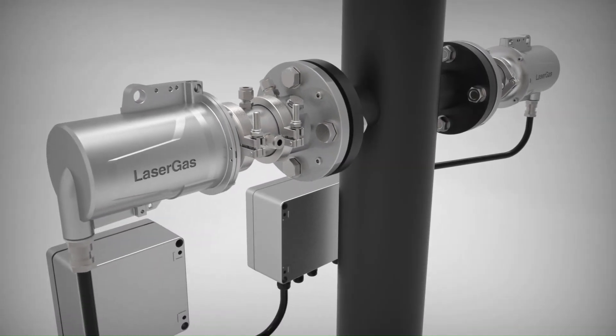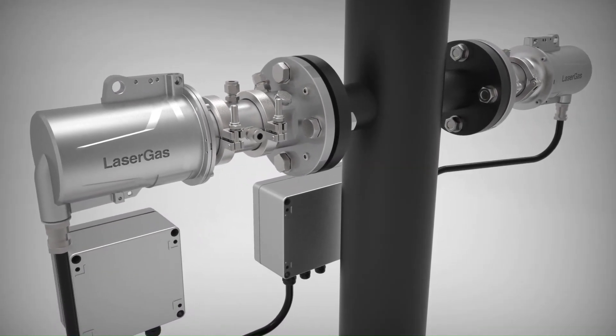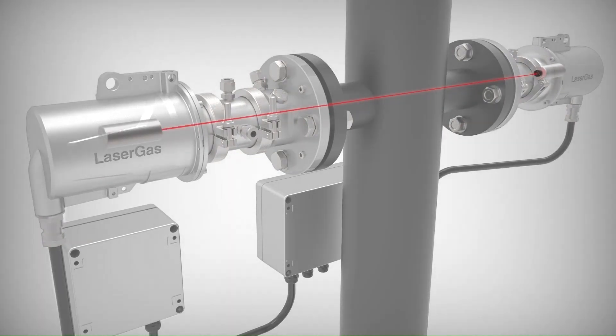The laser scans across the absorption line of the gas to be measured. The measured gas concentration is a function of the absorbed light in the process. The result is continuously reported.